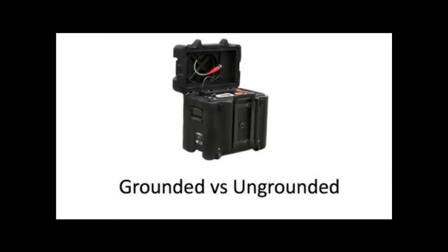This video will demonstrate how to connect your device under test, or DUT, and the 800PL DC series HiPOT in both return grounded mode and guard grounded mode. Incorrectly configuring the test setup connections or mode selections on the unit could lead to inaccurate results or incorrect readings.